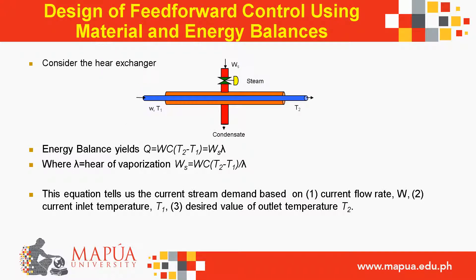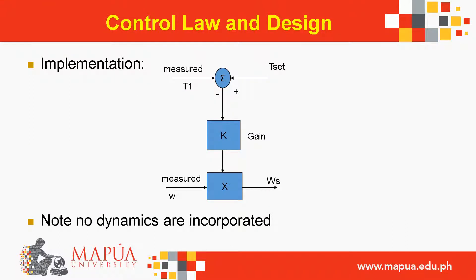Design of feedforward control using material and energy balances — consider the heat exchanger. Energy balance yields: Q = WC·(T2 − T1) = WS·λ, where λ is the heat of vaporization. Therefore WS = WC·(T2 − T1)/λ. This equation gives the steam demand based on current flow rate W, current inlet temperature T1, and desired outlet temperature T2. The control law design note: no dynamics are incorporated.